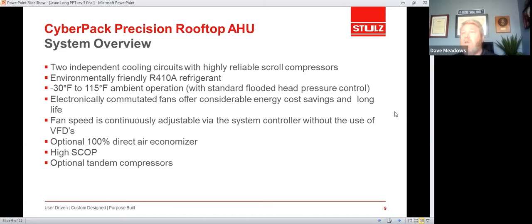And the reason for this is typically we do not want to strip moisture out of the airstream in a ITE or information technology equipment environment. And the reason for that is that at very low dew points, we see an increase in electrostatic discharge failures of the servers, switchgear, etc. We also offer these units with tandem compressors. What this does, these are two circuited systems. So one circuit would have two smaller compressors. The other circuit would have one full-size compressor. Coupled with the advanced controls of the Cyberpack, this gives us truly 4 distinct cooling capacities within that piece of equipment.